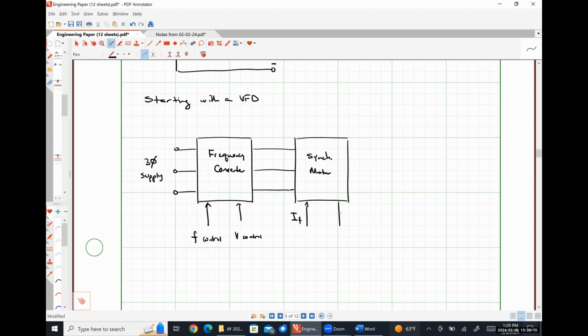So a system like this actually allows a synchronous motor to operate at literally any speed that can be provided by the variable frequency converter, right? So instead of always being a multiple of 3,600 RPM in the US, or 3,000 RPM in the EU, we can just spin it at any speed we want. Typically speaking, these variable frequency drives are usually kind of expensive, right? F control and V control. So we have control over both the frequency and the voltage that's being applied to the synchronous motor so that we can bring it up to speed safely. Because if we have the frequency too high, or way too high of a voltage at way too low of a frequency, we can burn things out.